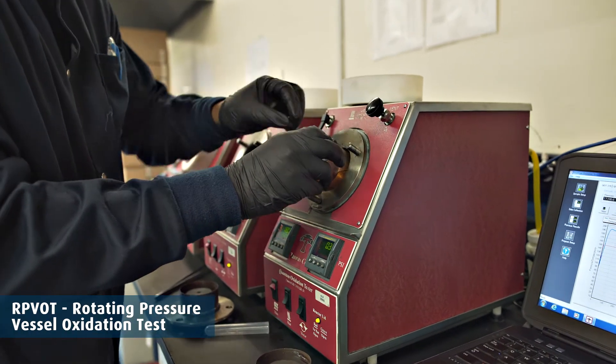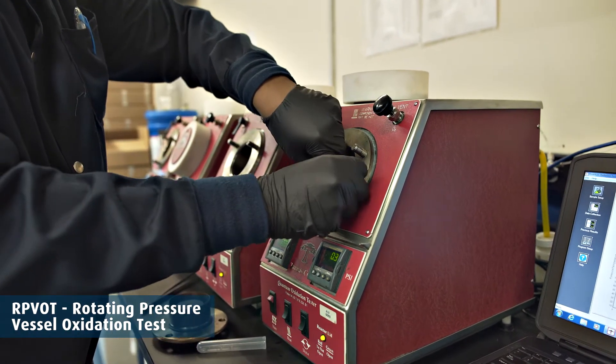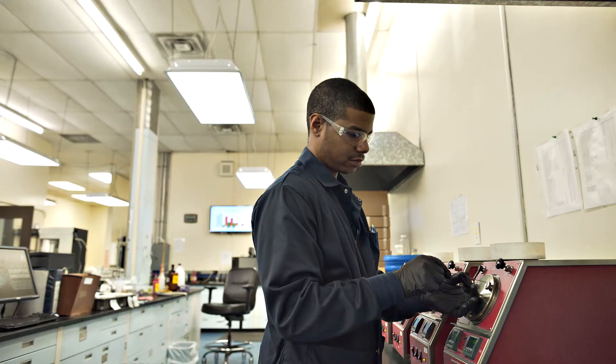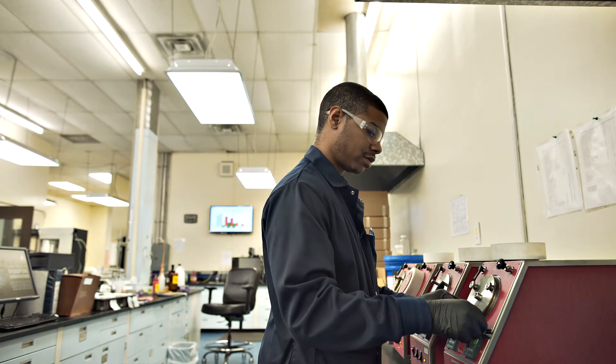RPVOT, rotating pressure vessel oxidation test, is a valuable additional tool as a direct measurement of fluid antioxidant performance and fluid service life.